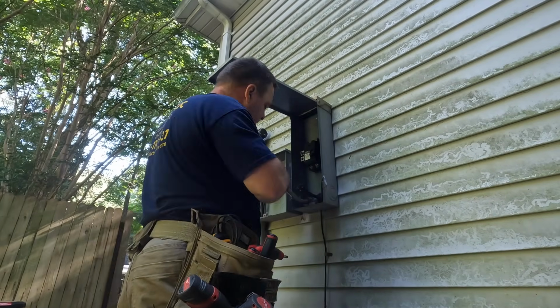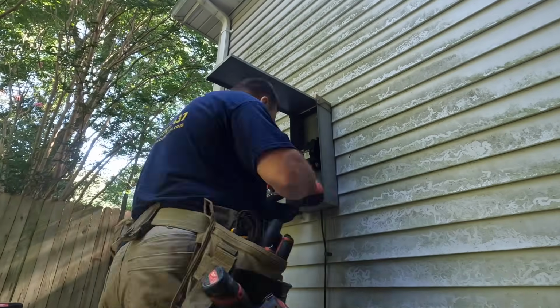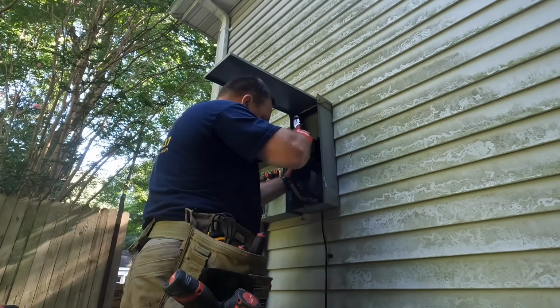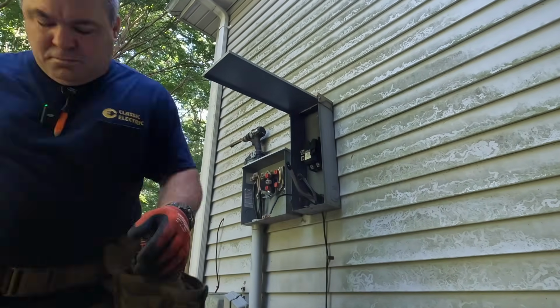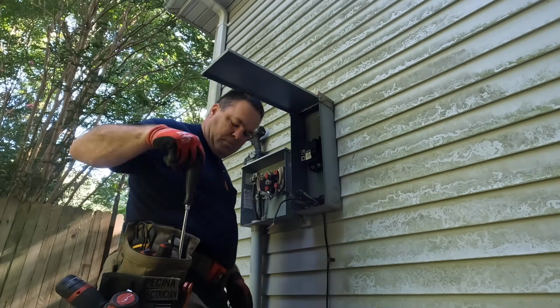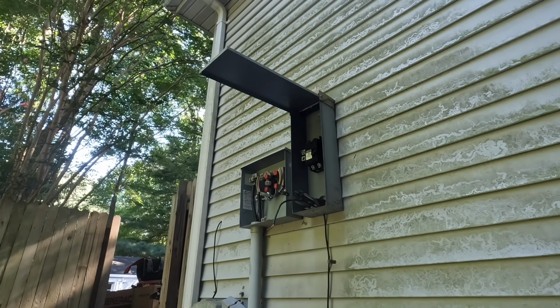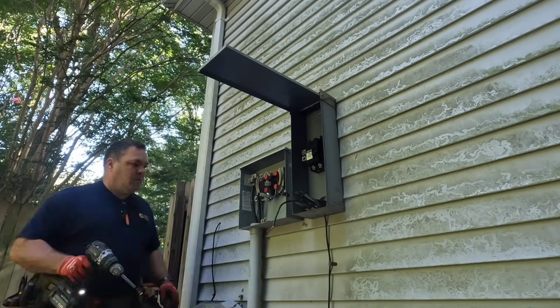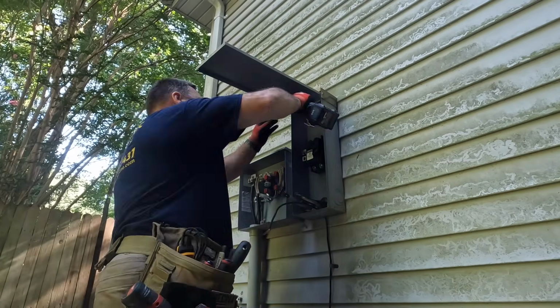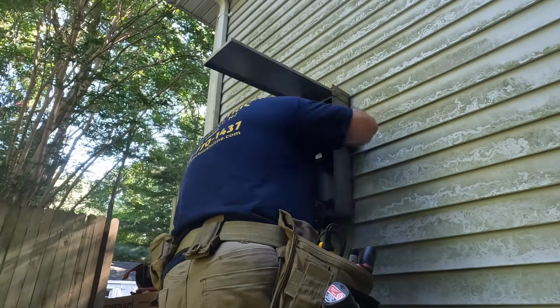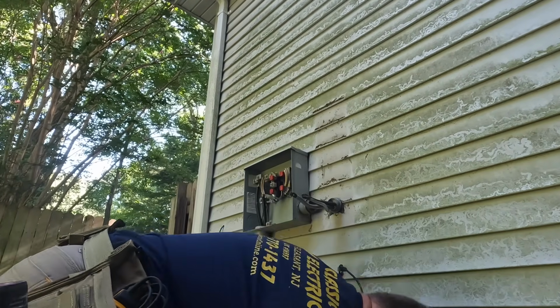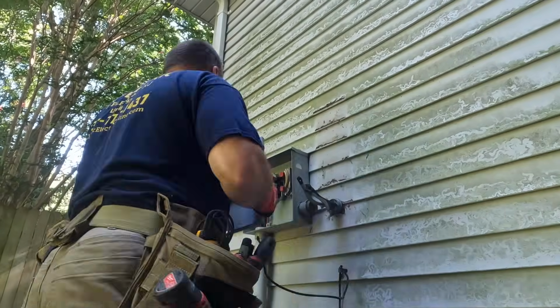The purpose of this section is to connect the grounding electrode conductor directly to the grounded conductor. And by doing that, it has to be on the same bus bar. If there's a wire, as like in the automatic transfer switch that bonds those two mechanical bus bars together, well then you can use either one of those bus bars. But you cannot depend upon the enclosure.